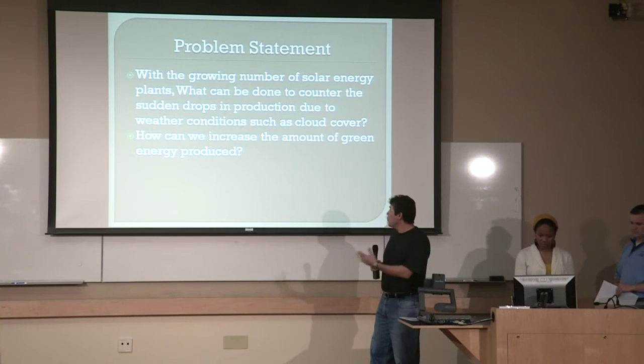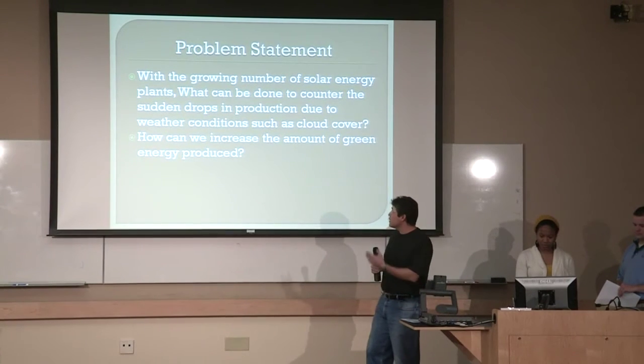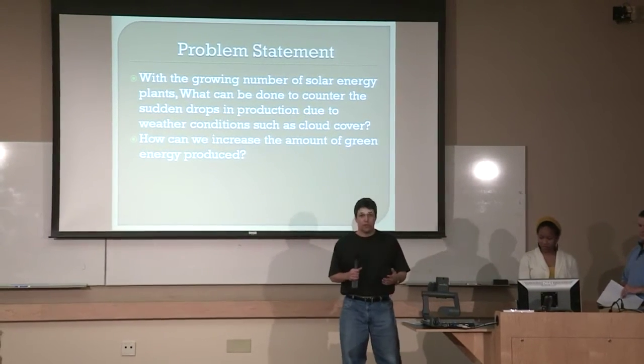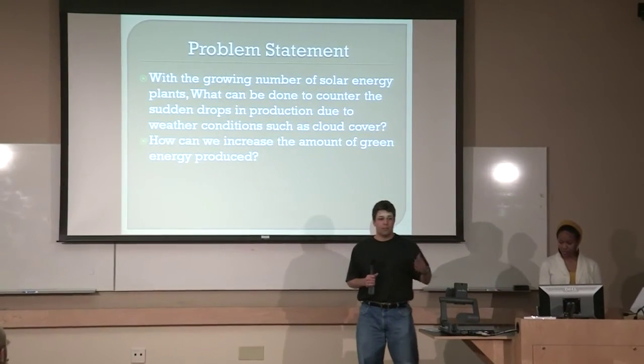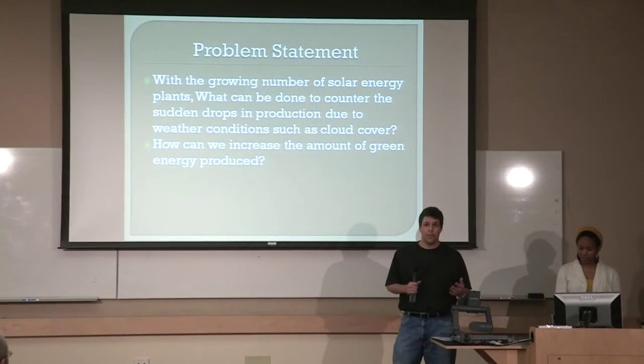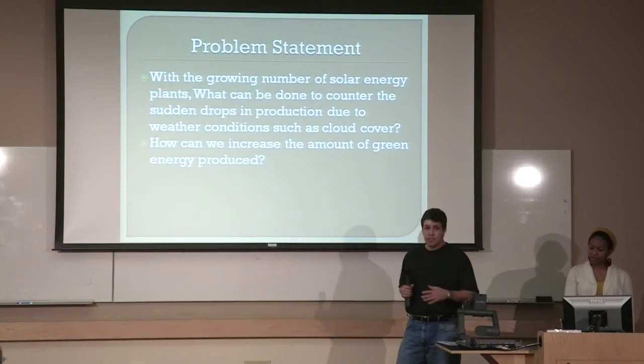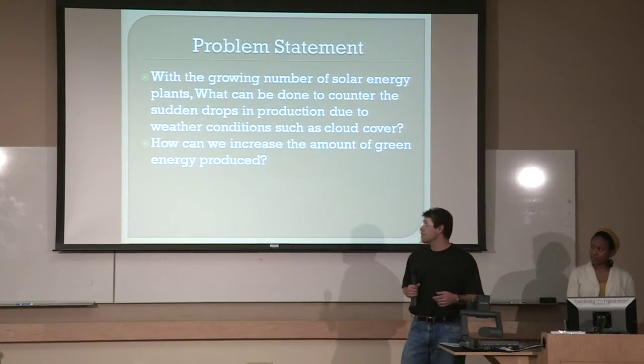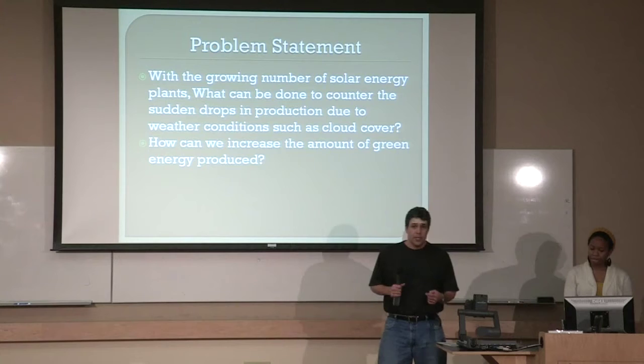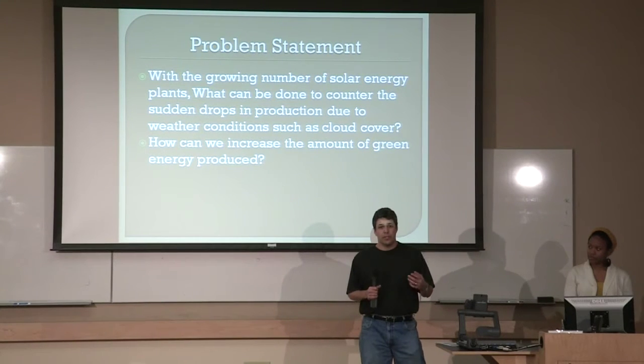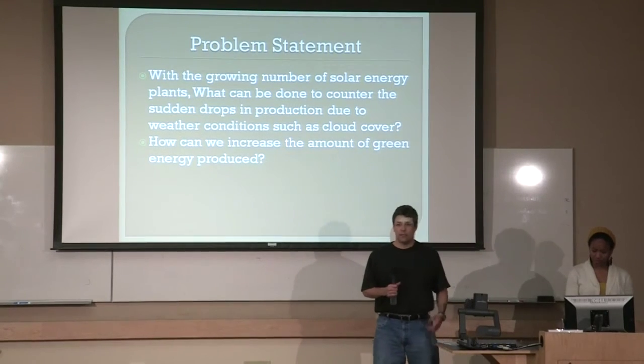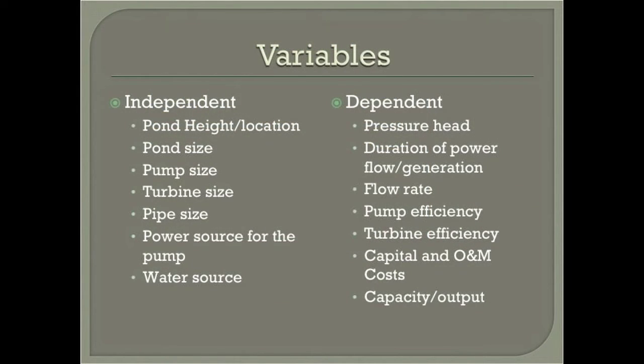With the inconsistencies or intermittencies of solar power, and as more solar power plants pop up around the valley, something needs to be done to compensate for this power loss. What we want to do is pump water using effluent water at the base of Sunrise Mountain up to a reservoir on top of the mountain, and then release it through the turbines whenever power is needed to compensate for losses due to solar power.